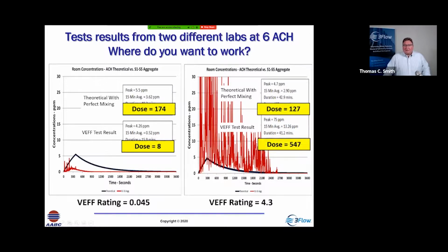On the right, same air change rate, 6 air changes per hour. The one on the right, the theoretical is 127, the actual is 547, a VEFF factor of 4.3. So which room would you rather work in? The one where it's removed, or one that's circulating around and stagnating in the space? So I think you would choose the one on the left.